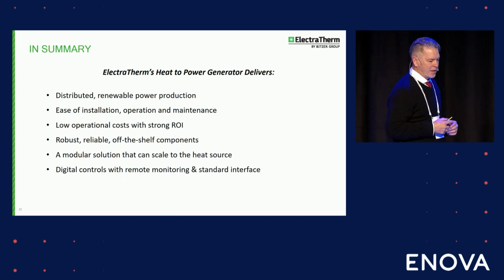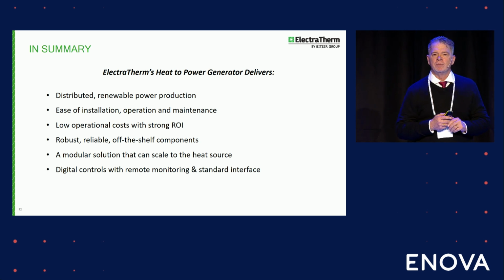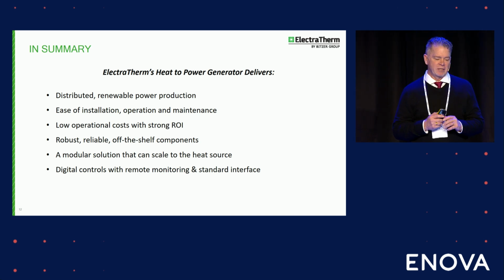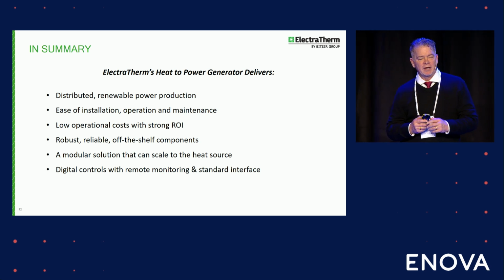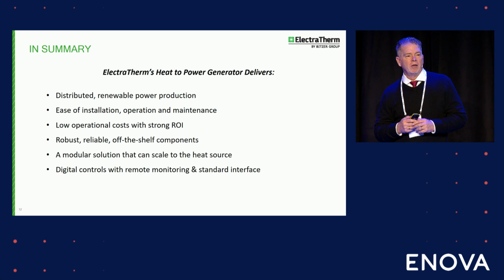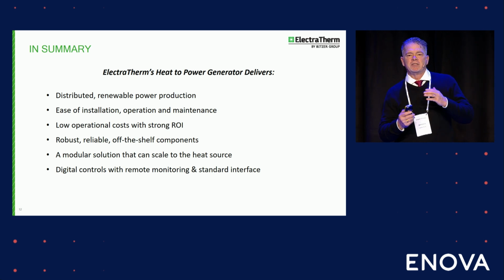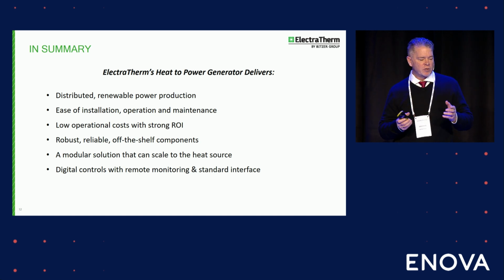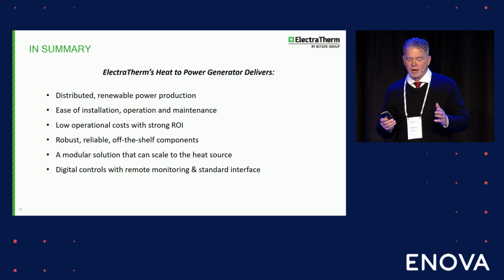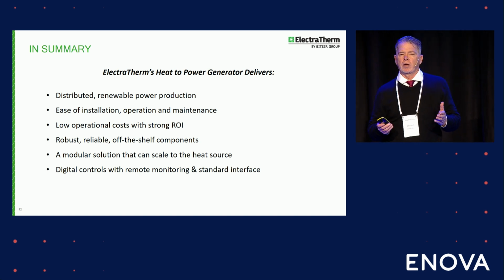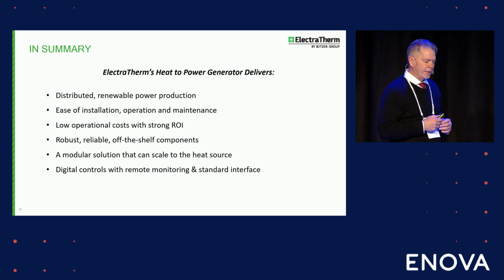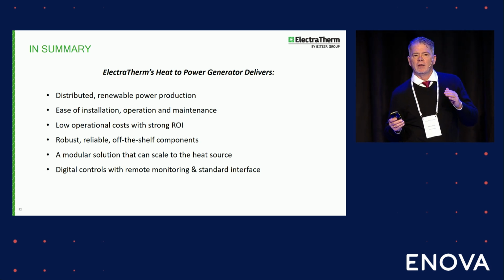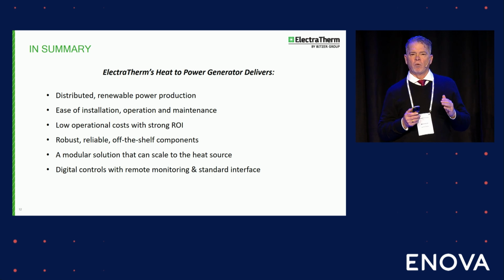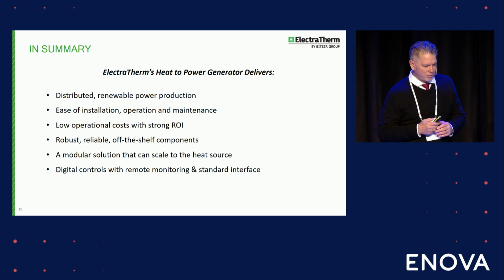Some final follow-up thoughts: we're really designed for distributed power generation—that's what we built the system to do. Ease of installation and maintenance is extremely low; we're talking small items every 6 months, and at the 30,000 hour point is where we finally have major maintenance on the equipment. Our low operational cost normally runs around 1 US cent per kilowatt for maintenance, and our levelized cost of power is about 5 to 6 US cents per kilowatt over the life cycle of the equipment—a very low levelized cost of power.